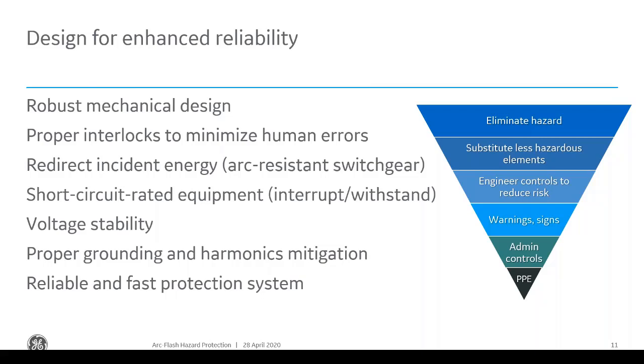Some of the enhanced reliability designs we can build into our system are engineering controls and design of the equipment, such as proper, robust mechanical design, sizing of all the equipment, and proper interlocks to minimize human errors. We'll talk a little more about that later. To redirect incident energy, we'll talk about how we do that with arc resistant switchgear. Short circuit rated equipment can interrupt and clear the fault in a specific amount of time. We also maintain our voltage, because voltage instability can cause insulation breakdown and deterioration over time. Then proper grounding and harmonics mitigation, and fast and reliable protection. A lot of the concentration later is on how we achieve arc flash mitigation using fast and reliable protection systems.